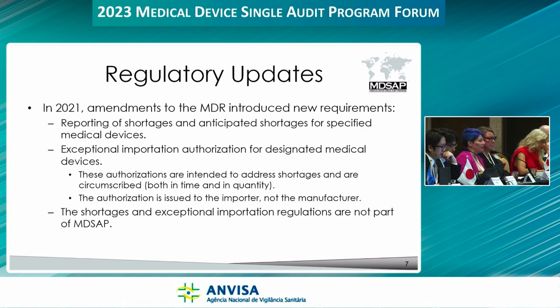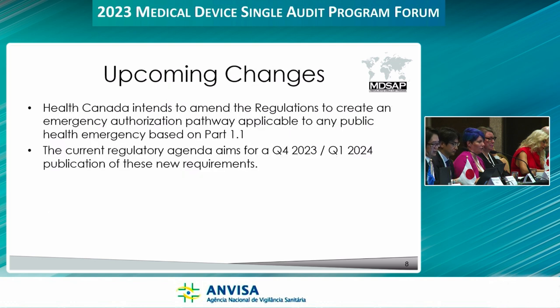Exceptional importation authorizations are designated for medical devices. These authorizations are intended to address shortages and are limited in both time and quantity. The authorization is issued to the importer and not the manufacturer. The shortage and exceptional importation regulations are not part of the MDSAP program and do not require an MDSAP regulation.